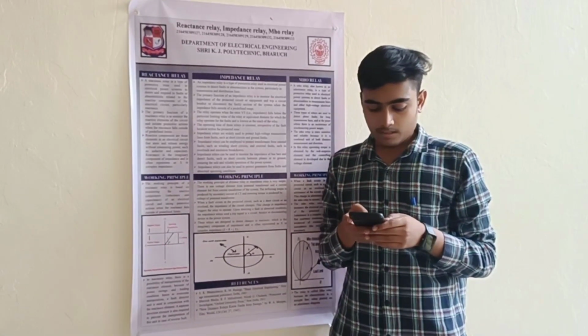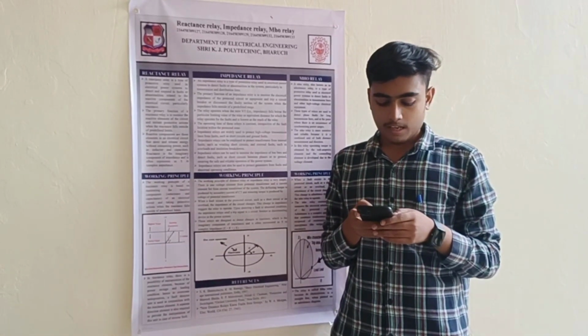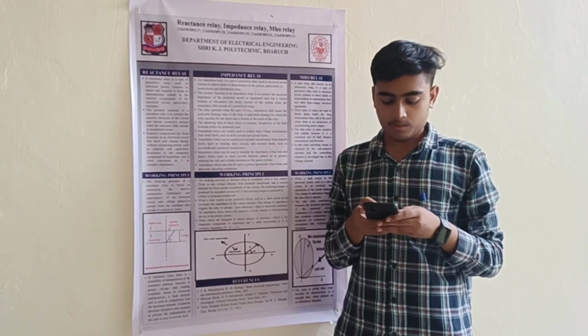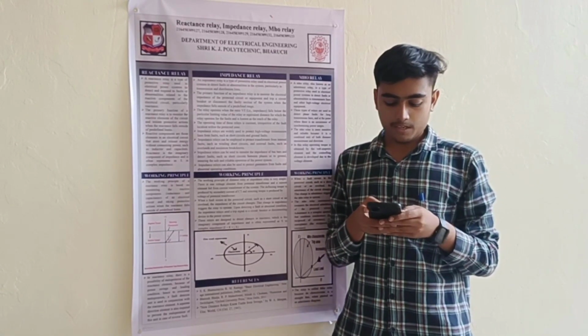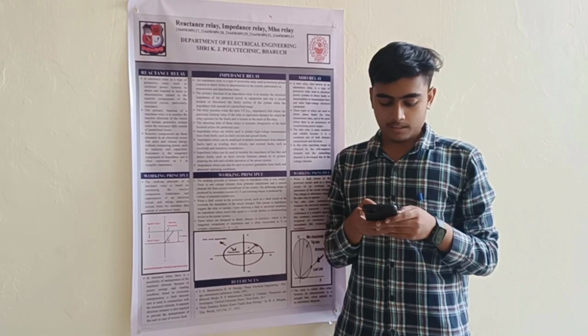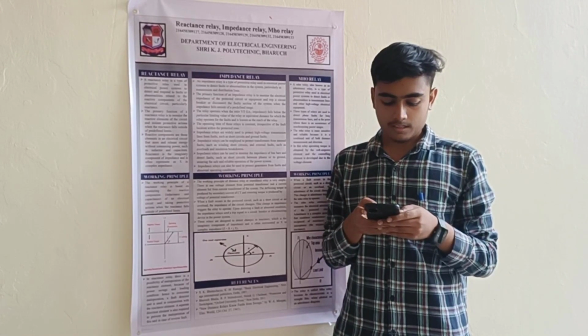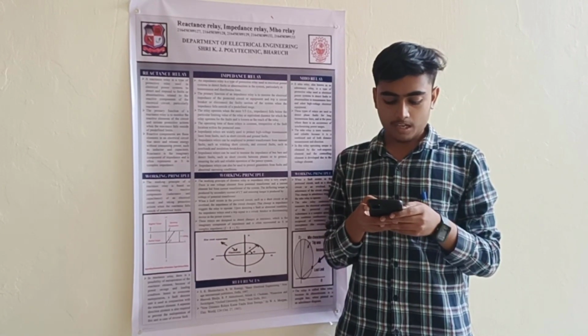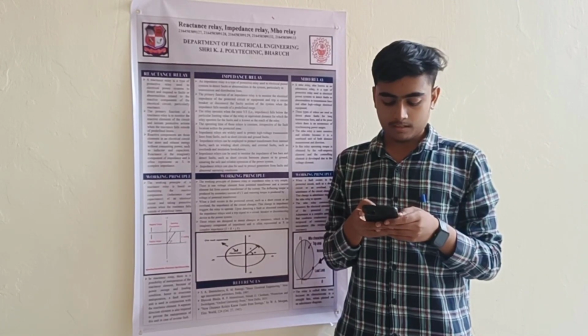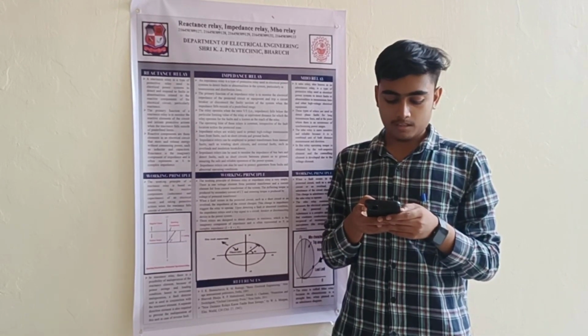Fifth, load shedding. In some cases, Mho relays can be used for load shedding purposes. By monitoring the impedance of the transmission line, the relay can detect high load conditions and initiate load shedding actions to prevent system overloading and voltage collapse.